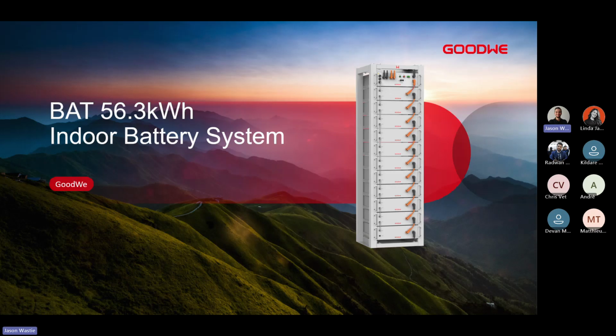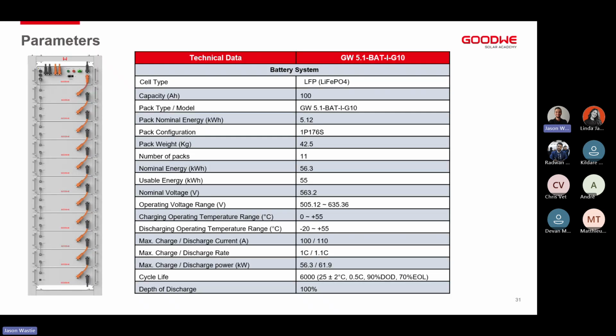However, the battery does come flat packed, which makes it easier for mobility, and easier for your installer to get it to site. However, obviously it does depend on the site itself. We can connect up to 6 of these batteries in parallel, so 6 batteries onto one ET50. It is 56 or 55 kilowatt hours of usable energy. So 55 kilowatt hours times 6 is 330 kilowatt hours per inverter. And if we do that times 10, it's 3.3 megawatt hours as a total. So we can go 500 kilowatts and 3.3 megawatt hours as a maximum on the system using this battery configuration.